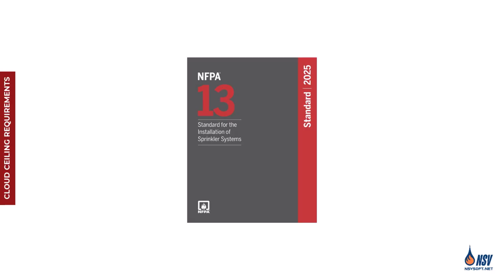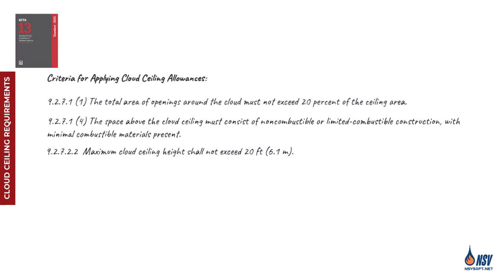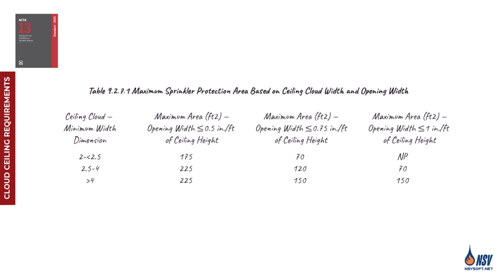In the 2025 edition of NFPA 13, the requirements for cloud ceilings are outlined in Section 9.2.7. These provisions allow for sprinklers above the cloud ceiling to be omitted under certain conditions. While some of these criteria are straightforward, the real complexity emerges when applying Table 9.2.7.1, which addresses the coverage area of sprinklers installed below the cloud ceiling.